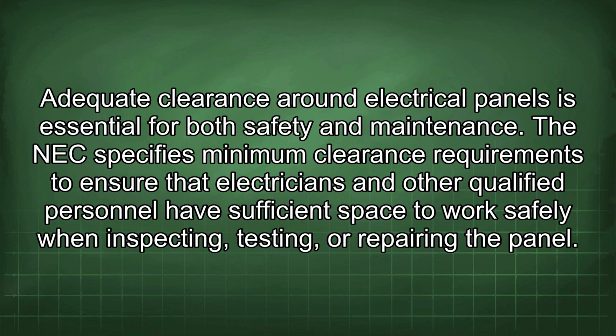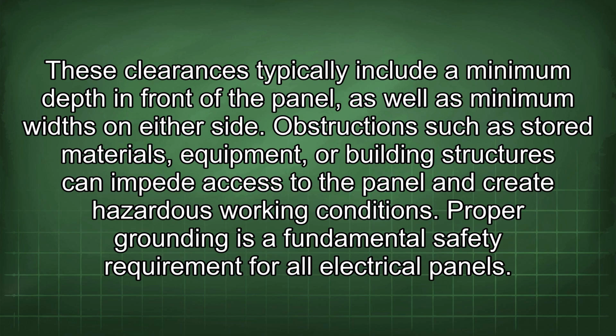Adequate clearance around electrical panels is essential for both safety and maintenance. The NEC specifies minimum clearance requirements to ensure that electricians and other qualified personnel have sufficient space to work safely when inspecting, testing, or repairing the panel. These clearances typically include a minimum depth in front of the panel, as well as minimum widths on either side. Obstructions such as stored materials, equipment, or building structures can impede access to the panel and create hazardous working conditions.